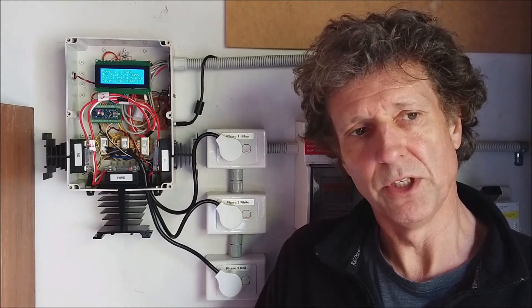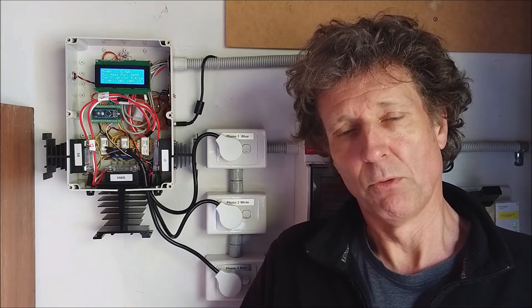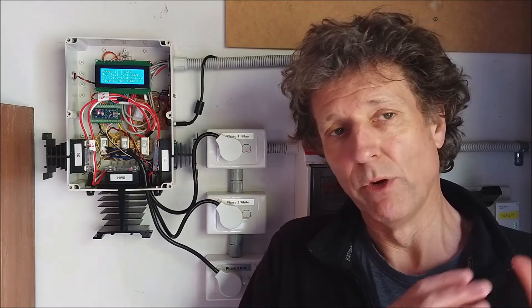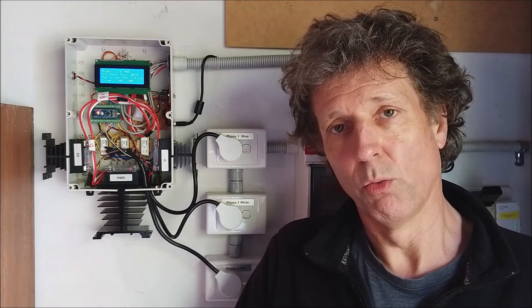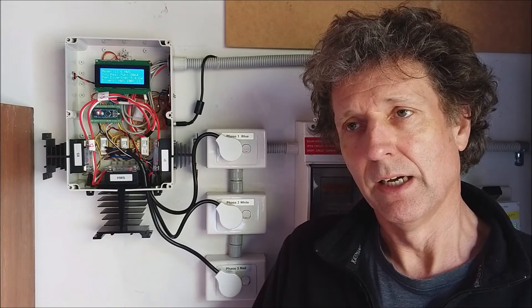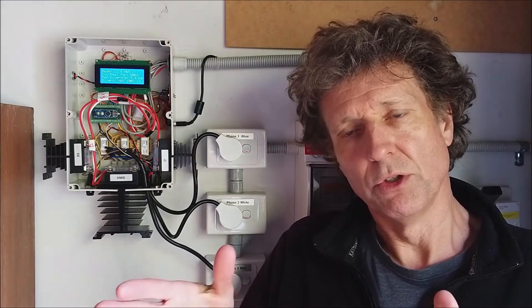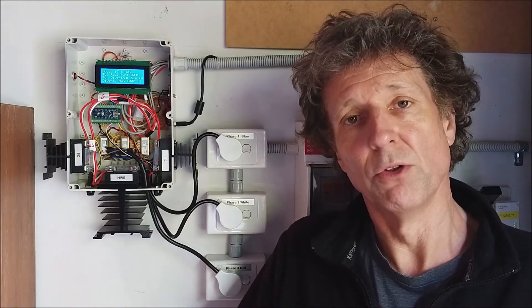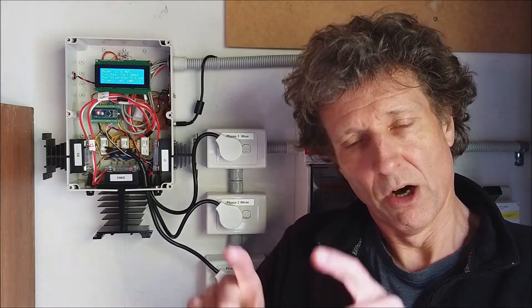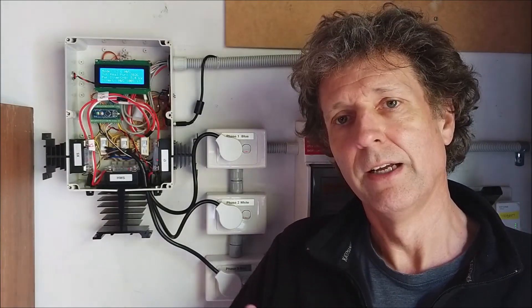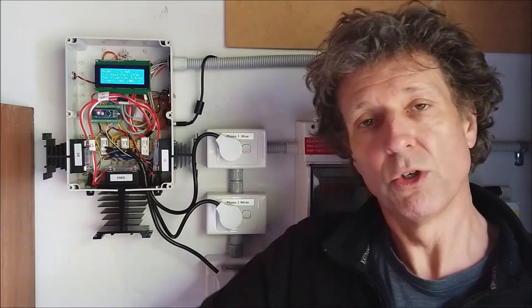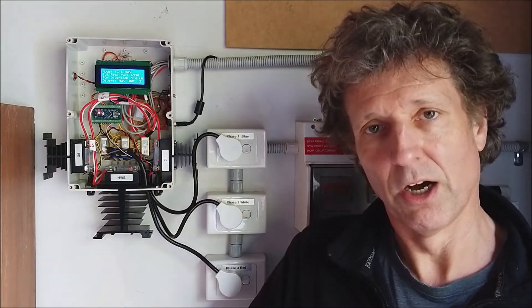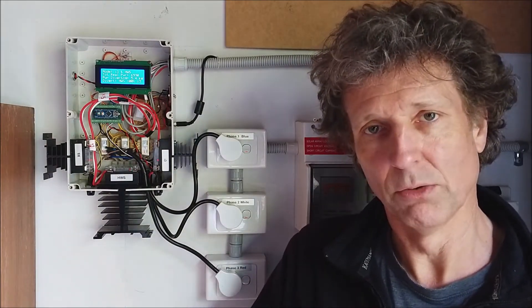If I give you an example, let's say we've got a 3.6 kilowatt element in the hot water service and we're exporting 1.8 kilowatts to the grid at any point in time or for that five second period. Then what I would do, I wouldn't run my hot water service for that entire five second period but I'd run it for only two and a half seconds or a 50% duty cycle. Now over a time period if I was to extrapolate that to an hour and everything being equal you could argue that I was exporting 1.8 kilowatt hours to the grid and my hot water service was switched on for half that time which is again 1.8 kilowatt hours.